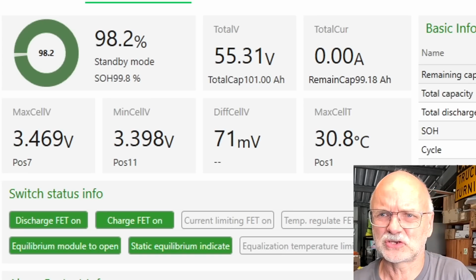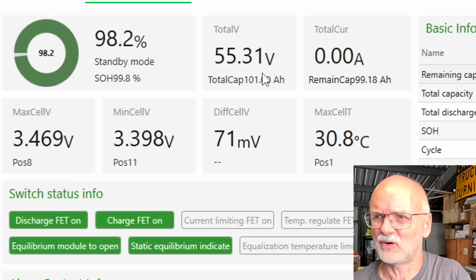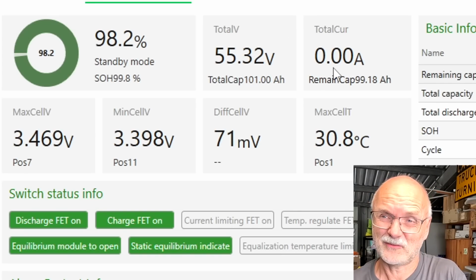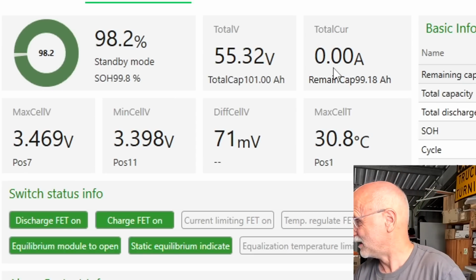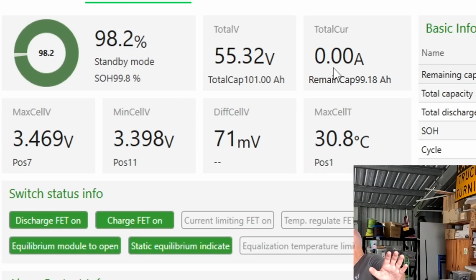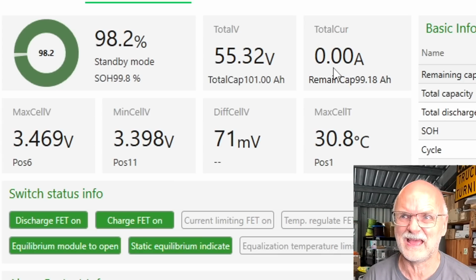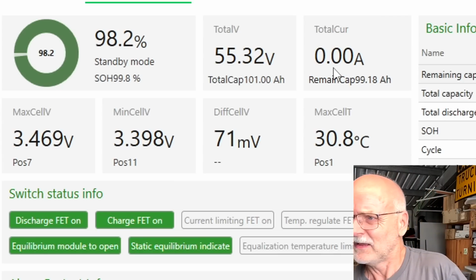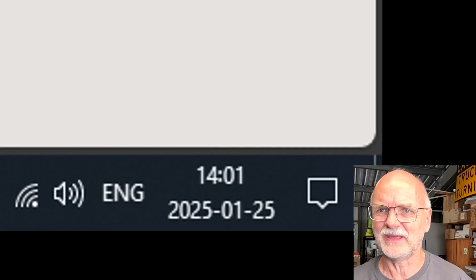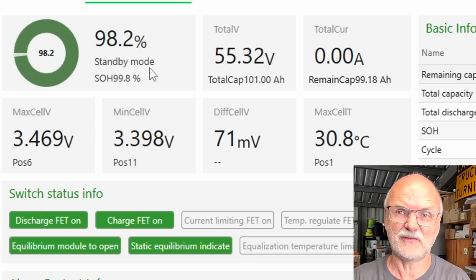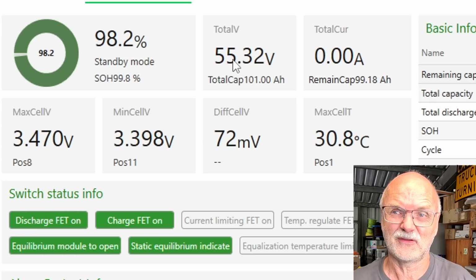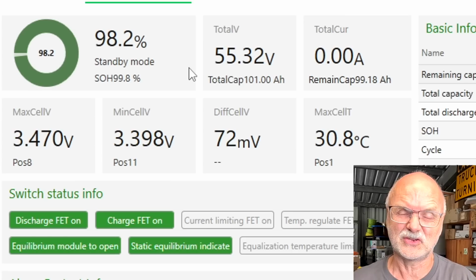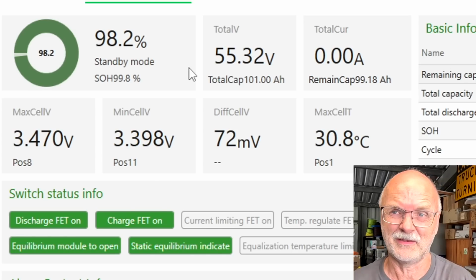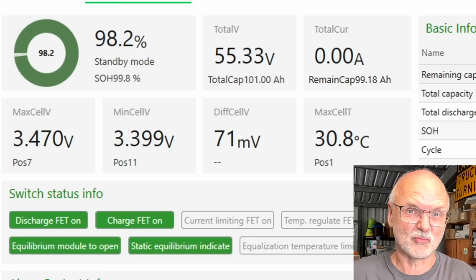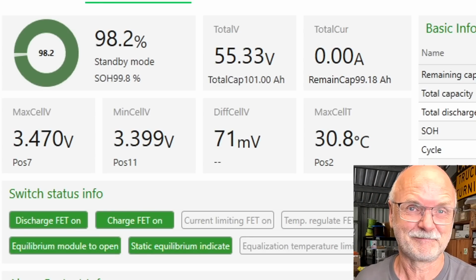So the BMS actually shows 55.3 volts now, but no current going into the battery - at least the BMS doesn't measure it. But we are still charging with 340 milliamps into this battery, and we now have exactly 2 p.m. We are on standby mode for 15 minutes and the voltage is above 55.2 volts. This should meet requirement number 1 and we should see 100% state of charge. But this is not real world conditions, obviously.